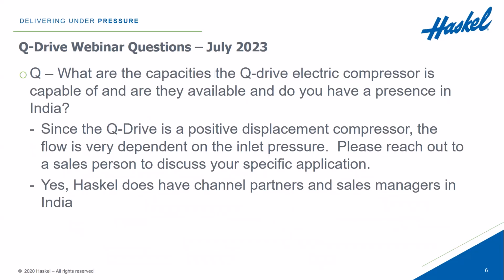What are the capacities of the Q drive electric compressor and capability, and are they available? And do you have a presence in India? Since the Q drive is a positive displacement compressor, and we can handle a variety of inlet conditions, the flow is very dependent upon the inlet pressure. Obviously, the more inlet pressure I have, that means the more molecules are being pushed into that compression chamber, so the more gas flow I'm going to have. So it's really hard to answer that question without getting a better handle on what your conditions are. So please reach out to a Haskel salesperson or channel partner, and they can help answer the question for your specific needs. And yes, Haskel does have channel partners and sales managers in India to support Q drive or any Haskel products in that area.